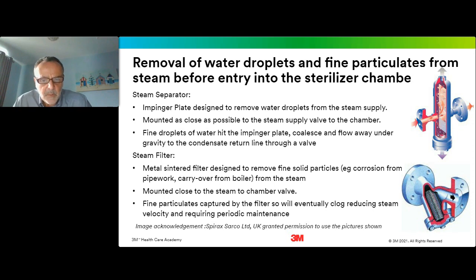Now, I know that many people will also have steam filters in the steam supply line to remove fine solid particles, such as fine particles of corrosion that might have come from iron-based pipework. And this, again, should be mounted close to the steam-to-chamber valve so that the particles are removed immediately before the steam enters the sterilizer chamber.